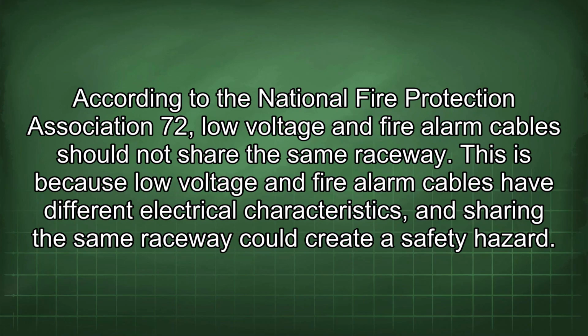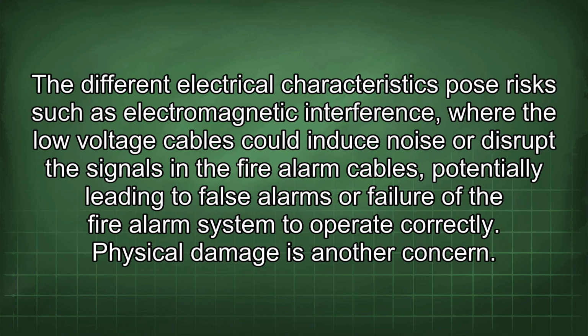According to the National Fire Protection Association 72, low voltage and fire alarm cables should not share the same raceway. This is because low voltage and fire alarm cables have different electrical characteristics, and sharing the same raceway could create a safety hazard. The different electrical characteristics pose risks such as electromagnetic interference, where the low voltage cables could induce noise or disrupt the signals in the fire alarm cables, potentially leading to false alarms or failure of the fire alarm system to operate correctly.